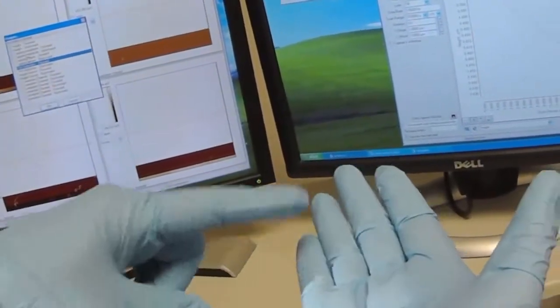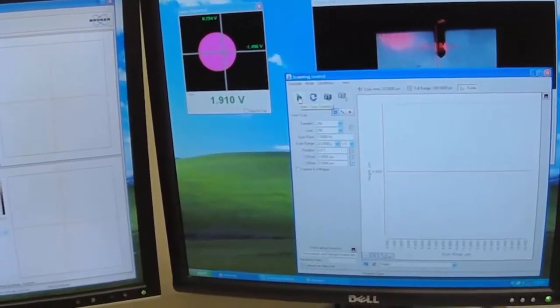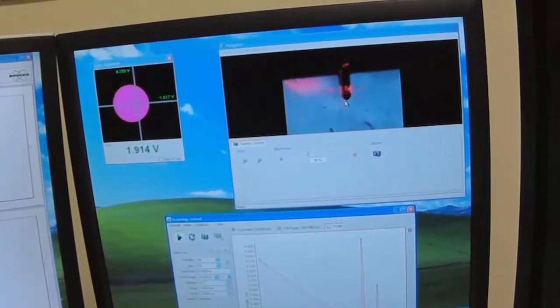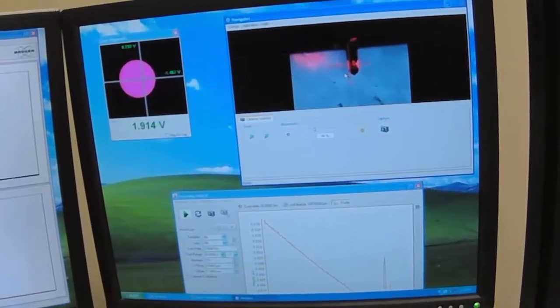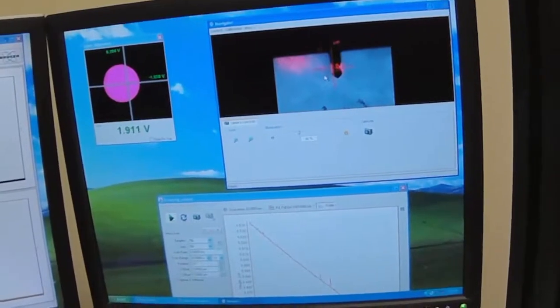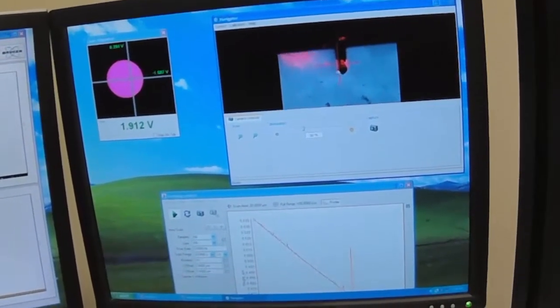And then let's look at amplitude. The amplitude is how much the tip is vibrating. When it encounters an object on the surface, that causes a change in the amplitude, and it'll be abrupt, and that actually helps us see edges of objects. So we press the play arrow, and you can see the cantilever is moving back and forth, so this is our X direction, and every time it goes back and forth a cycle, it moves up in Y, this is the Y direction, and does another scan.